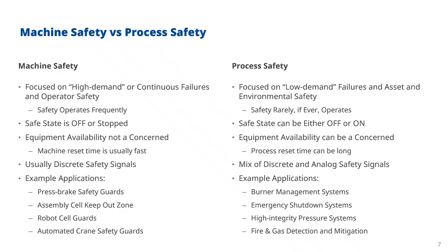Equipment availability can be a concern. Because process reset times can be long, you ideally want a process safety system that's also reliable. If a safety system trips, then that's not an issue from a safety point of view because the system is safe. But if you're running an oil refinery that is very expensive and needs to run 24/7, then you don't want it tripping spuriously. Instead, you have a more reliable system with higher levels of availability so that you don't have to worry about shutting the system down. And again, there's a difference there.